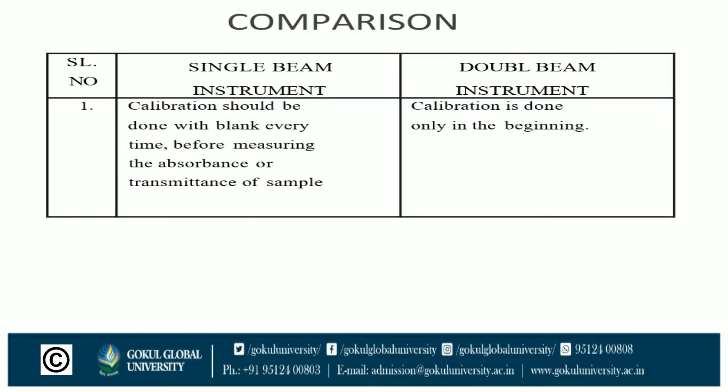Here is a comparison of both single and double beam spectrophotometers. For calibration: in the single beam, calibration should be done with a blank every time before measuring the absorbance or transmittance of a sample. In the double beam, calibration is done only once at the beginning.